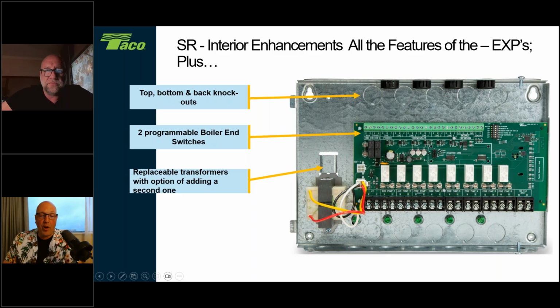So right now, this 20 VA transformer is going to be able to power this board itself and the relays and your standard not power hungry thermostats, maybe a thermostat that's got a couple of batteries and some power stealing stats, but not your Wi-Fi design. All right, so that's when you might want to drop in that 40 VA. All right, and everybody should be, if they've got this control in stock, they should be able to get you a 40 VA plug in and you just drop it right in. That was also a big change from the Dash 4s. For example, if we had 2 transformers on here, Transformer 1 covered half the board, Transformer 2 covered the other half. Now what we have is that both transformers can share their power across the entire board, okay?